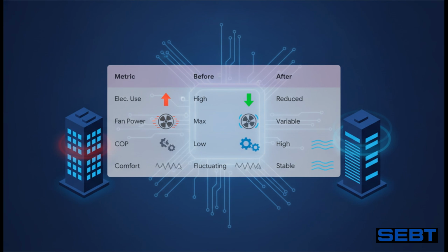Now, what's really interesting about this slide is just how dramatic the results are when the PLC and BMS are perfectly integrated. Just look at the before and after. Before optimization, electrical consumption was sky high and fan power was just constantly blasting at maximum. After optimization, consumption is drastically reduced, primarily because our fans are now variable. They're driven by VFDs to use only as much power as absolutely needed. The coefficient of performance jumps from terribly low to incredibly high. And as for the actual people inside the building, they go from sitting in a fluctuating, uncomfortable environment to one that is just flawlessly stable.